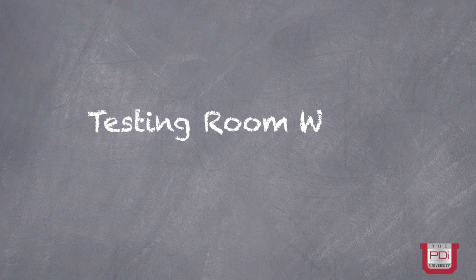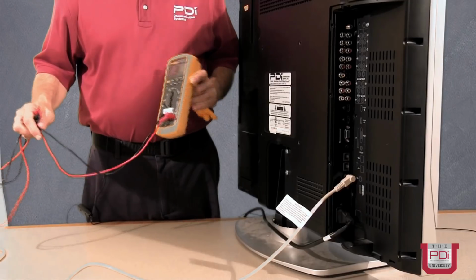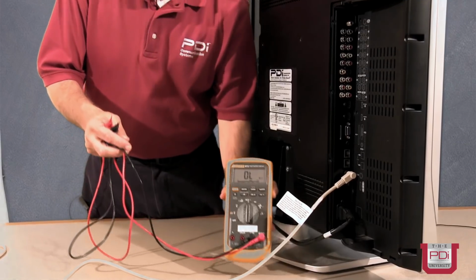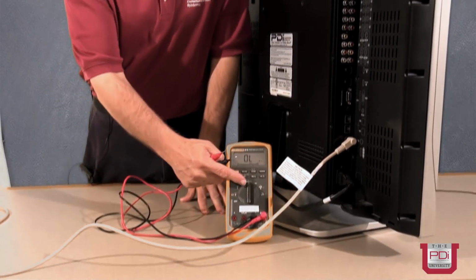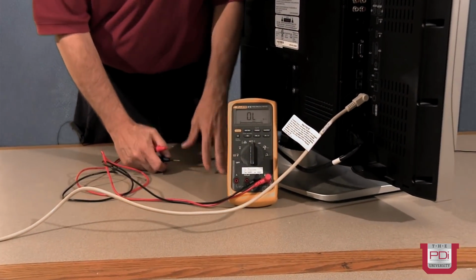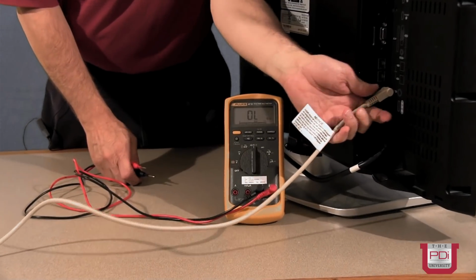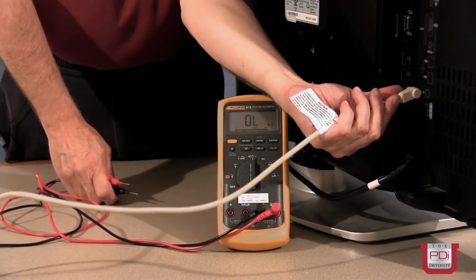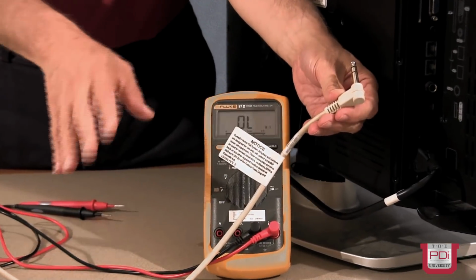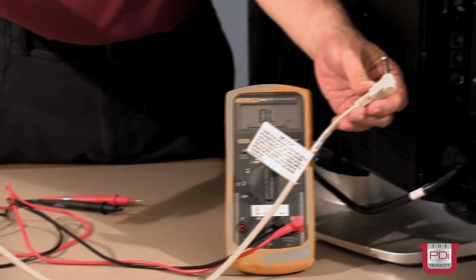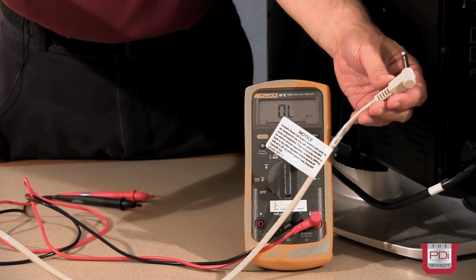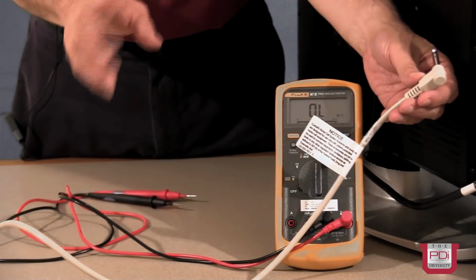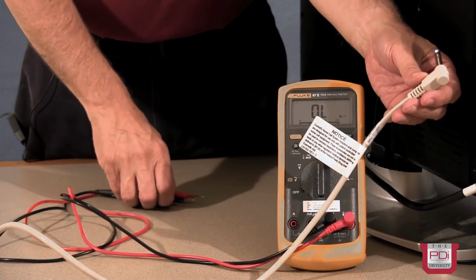The next step would be to ring out the wiring in your room. And the easiest way to do that is with a volt-ohm meter. Set it to the resistance range and simply unplug the pillow speaker jumper cable from the TV, remembering to keep it plugged into the wall plate behind the TV, and at the same time you need to make sure that the pillow speaker is connected.